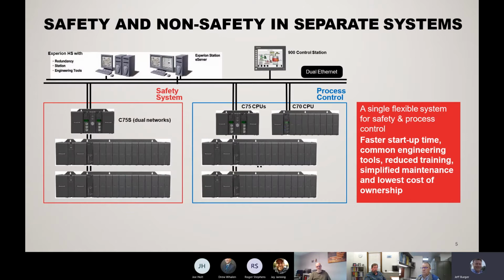The safety and non-safety I/O and CPU can live in separate systems, so some customers will actually separate out these two and have the safety system just taking care of those parts of the process, and then the other process control environment, which doesn't require the high level of security, they'll have that separated out into a different architecture. Both of these systems, if they're separated out, will look as if they are one system as they communicate up to a SCADA system or the HC900 control station. So it looks as basically one common platform when you're viewing it at that level, but down at the I/O level they separate it out and allow these CPUs to communicate across the network and share information between the two systems.